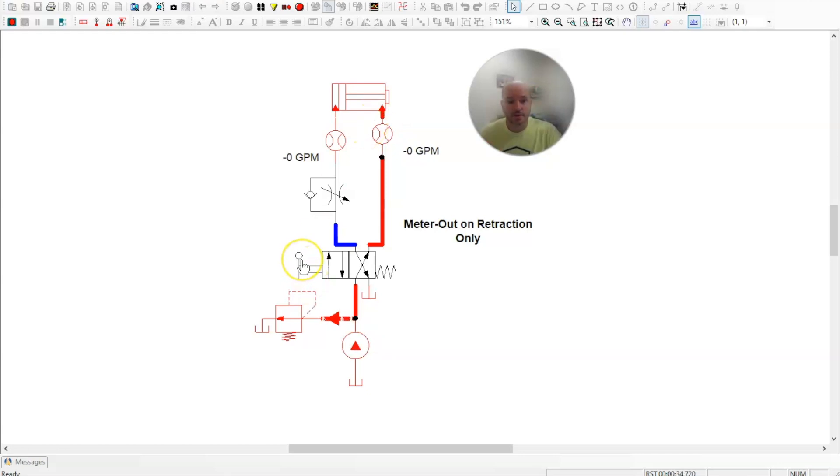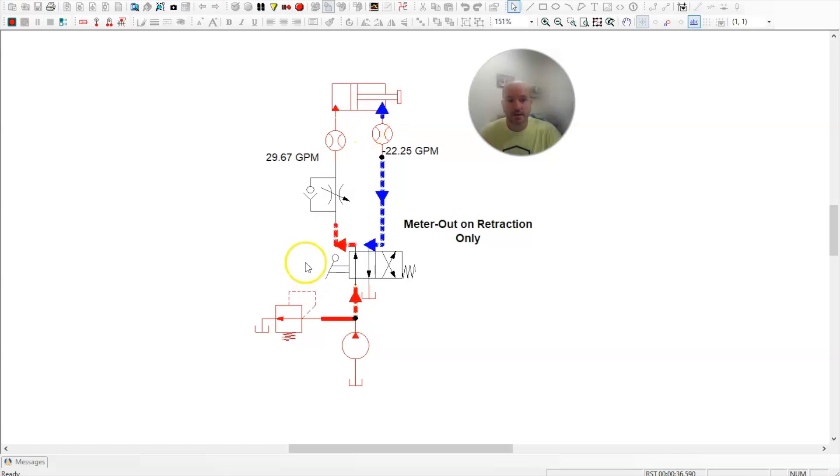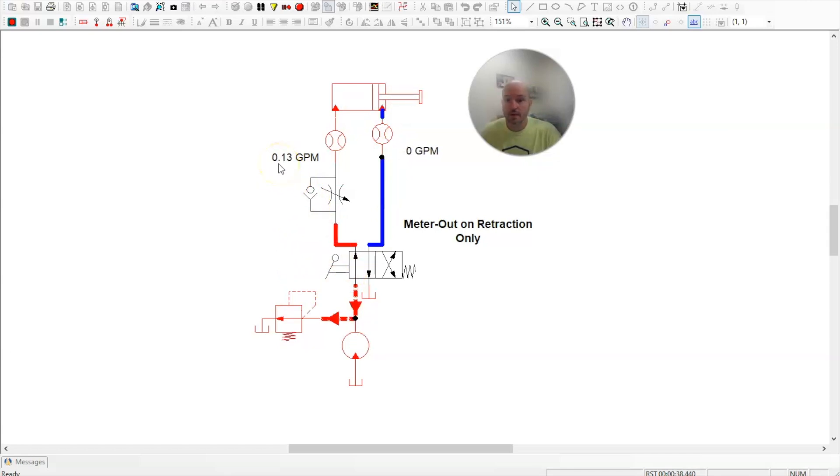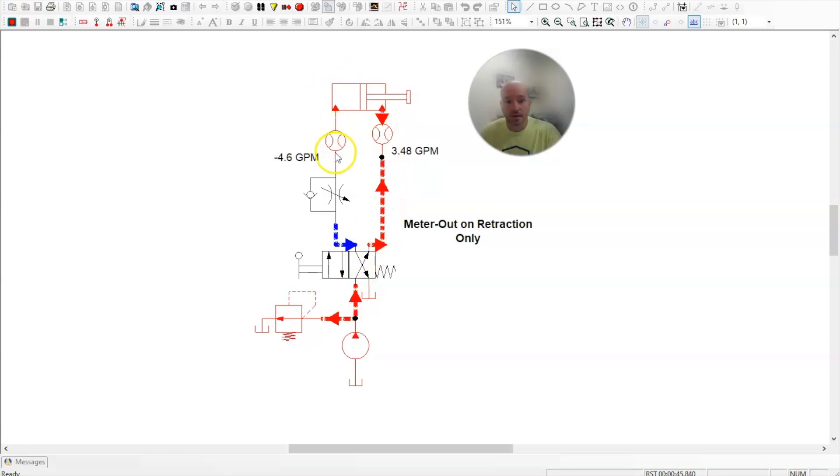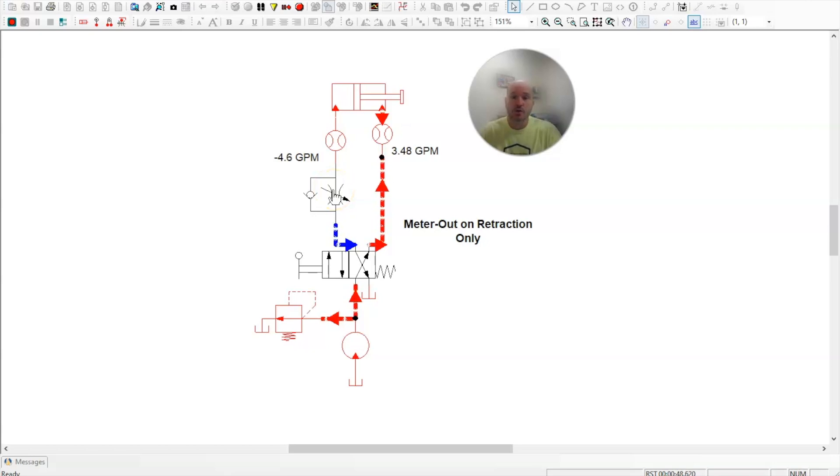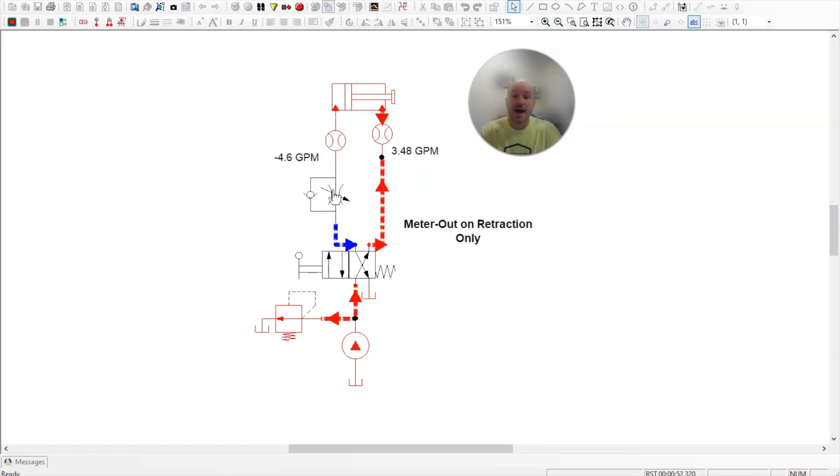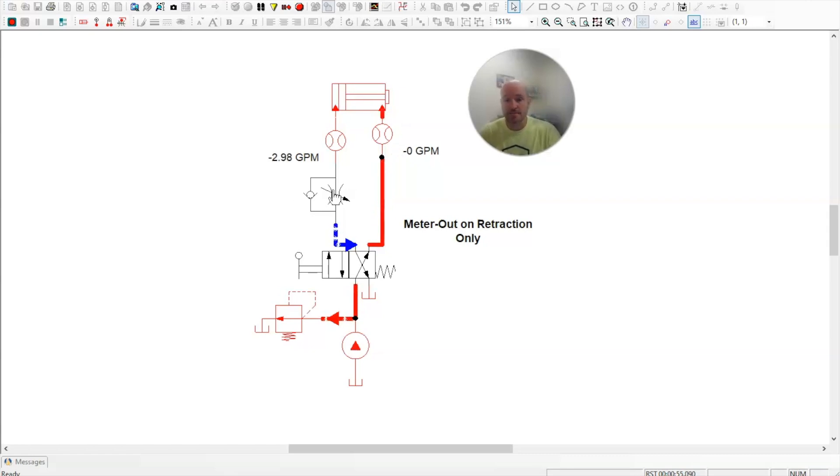Let's watch it one more time. I'll activate the cylinder. It will go out fast going at about 30 gallons per minute. Then when I go to retract the cylinder, it will force through here. All of the oil here has to get forced through the needle valve. So it meters the oil as it exits the cylinder or as it goes out of the cylinder. That's why it's called a meter out circuit.